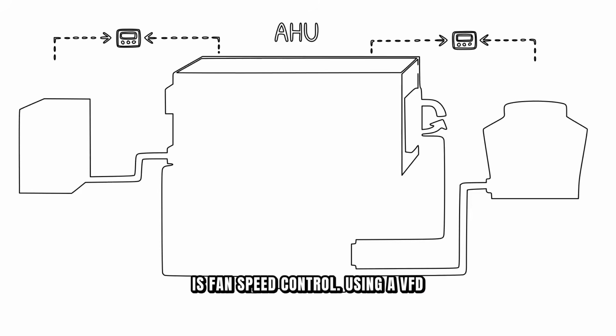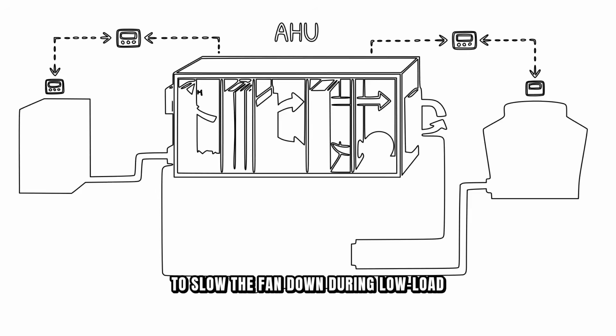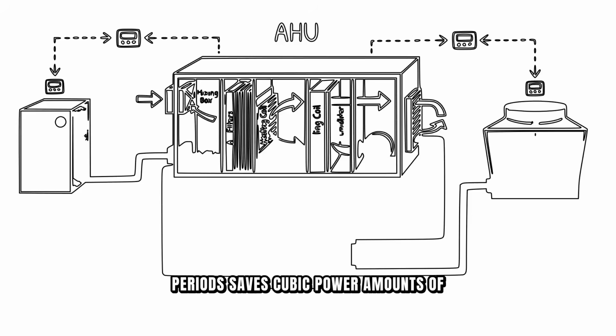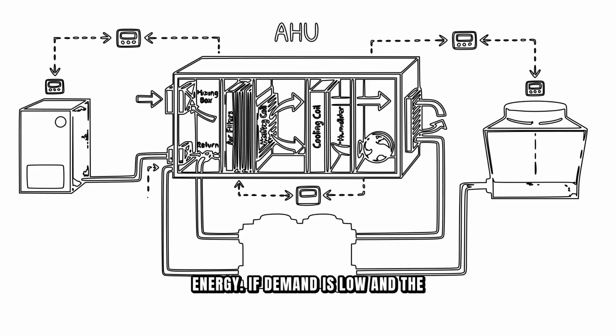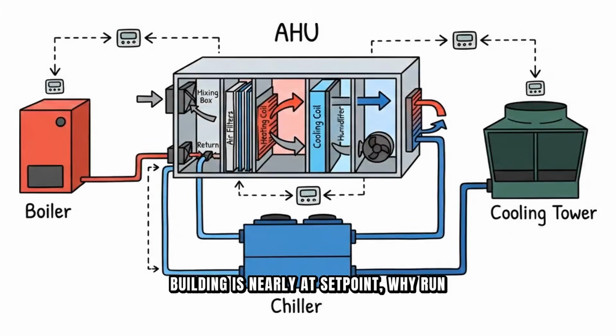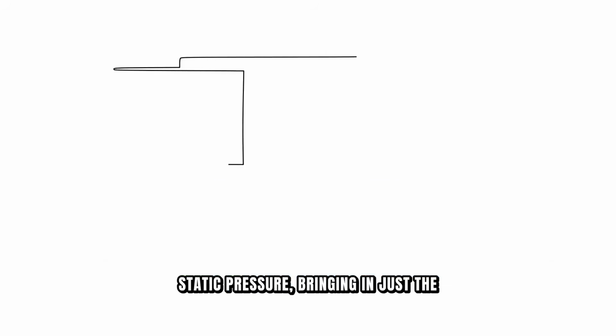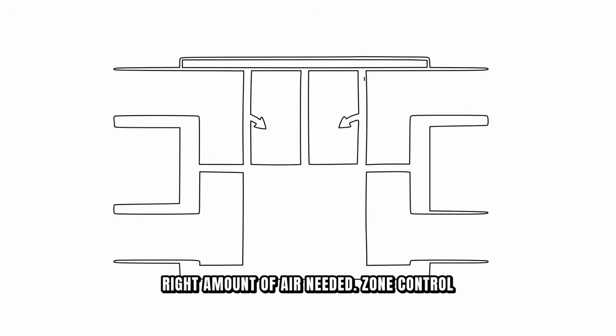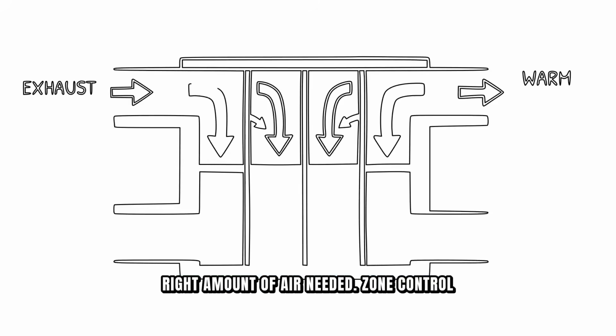Another optimization is fan speed control. Using a VFD to slow the fan down during low load periods saves cubic power amounts of energy. If demand is low and the building is nearly at set point, why run the fan at full speed? Modern systems modulate fan speed based on actual ductwork static pressure, bringing in just the right amount of air needed.